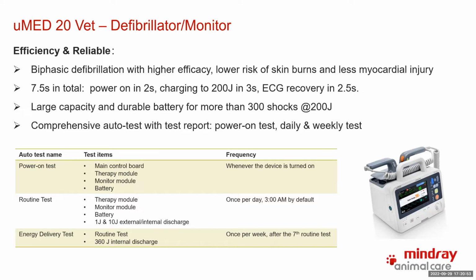Also, for a defibrillator, if I turn on the machine and find out it cannot work, that would be a very serious problem, because all the patients who need a defibrillator are very critical. So for our uMED 20 vet, we support a comprehensive auto test with a test report. The machine can do the power-on test and also daily and weekly tests. For power-on, it automatically tests that all the modules function well, and the routine test also checks the external and internal discharge. They also do a weekly test for the energy delivery.